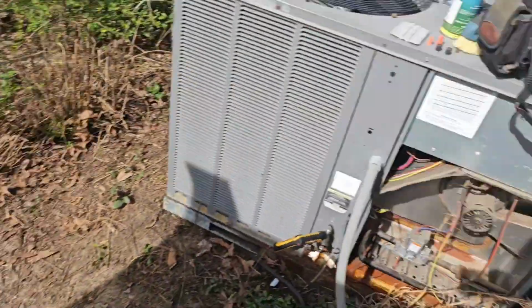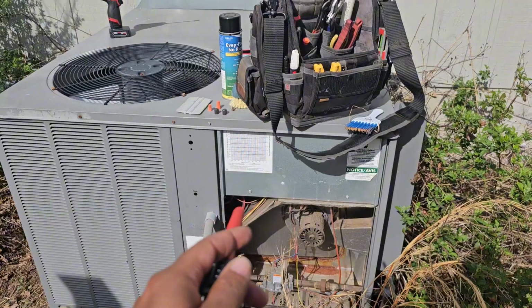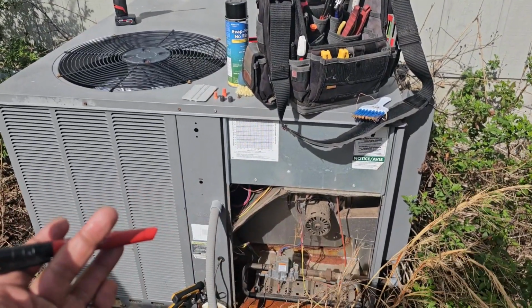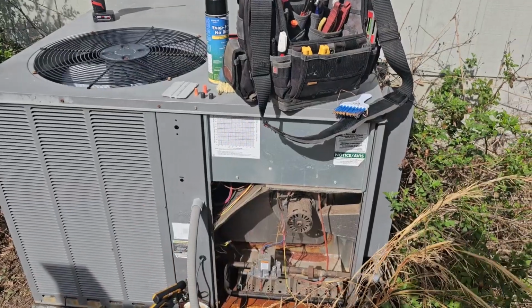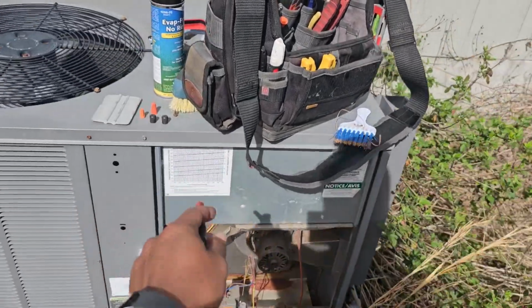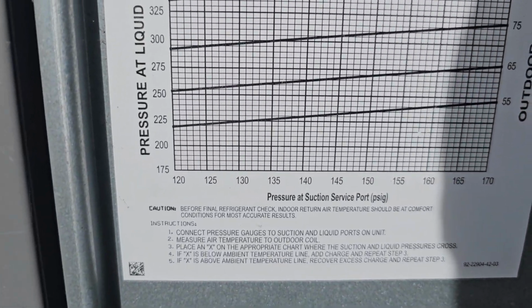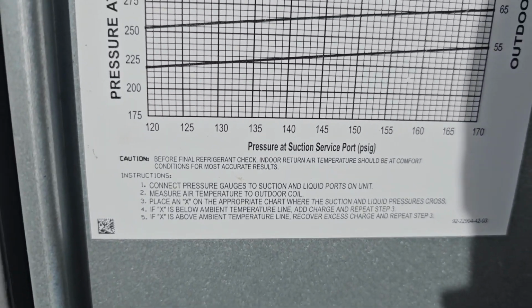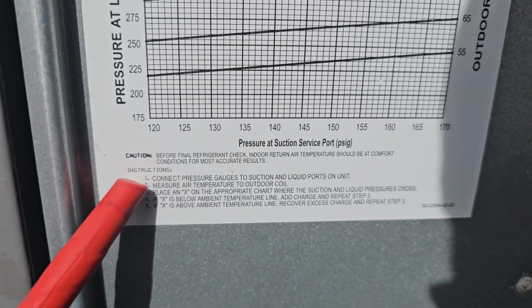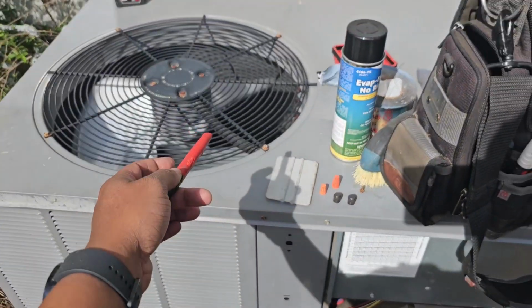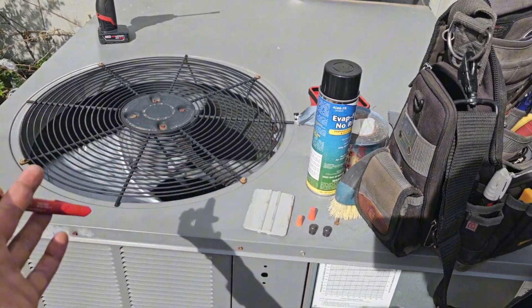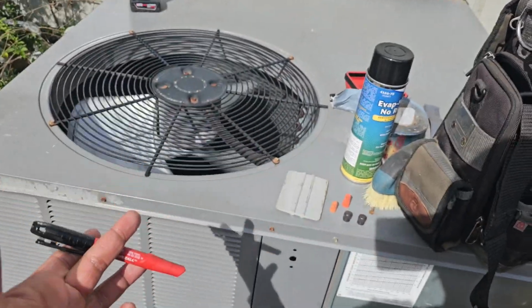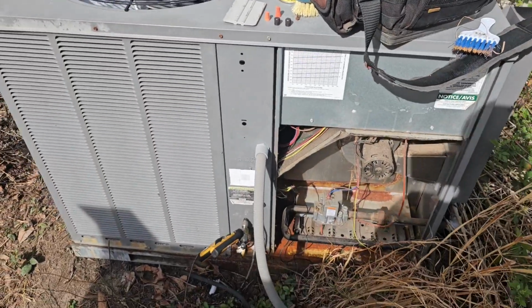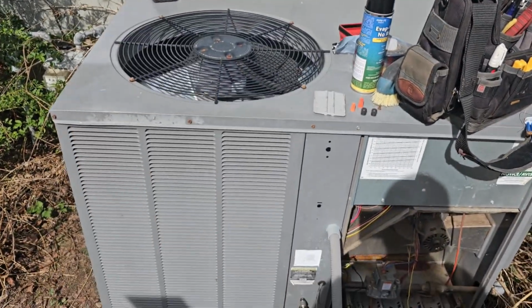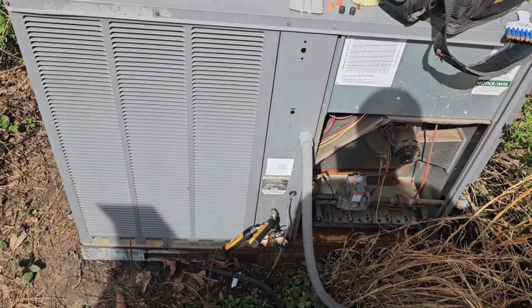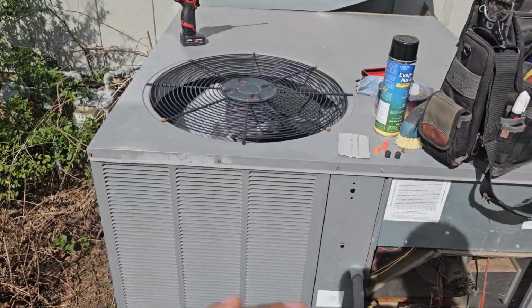One thing that has always bugged me about Rheem doing their pressure charts is that I don't know how they have it set up to where they don't even care about your superheat, subcool, they just want you to go based off those pressures. I have seen on some of these where they would tell you your TXV subcool, but without being able to put your clamps on there, you wouldn't be able to know. And unless you had Bluetooth clamps, you really wouldn't be able to know, because if you had just a regular 3 or 4 port gauge manifold, how are you going to clamp onto anything to get your temperatures? So this is one of those instances where having the Bluetooth stuff really pays off.